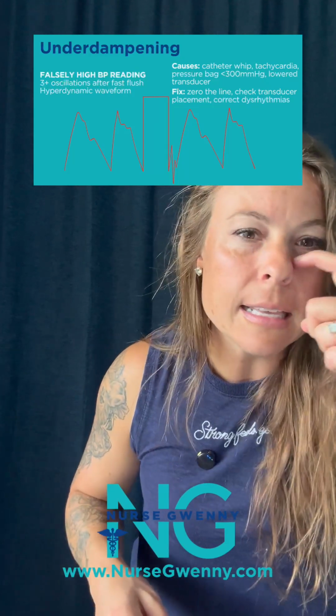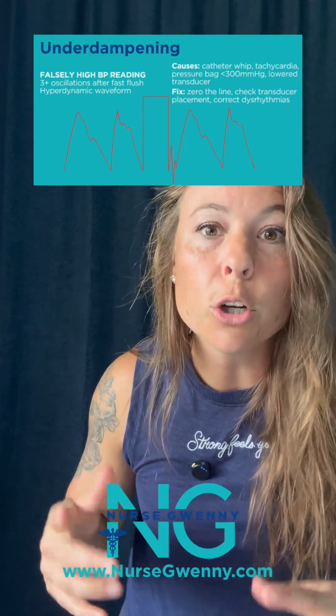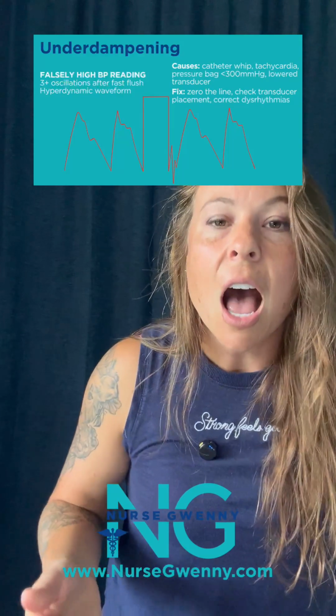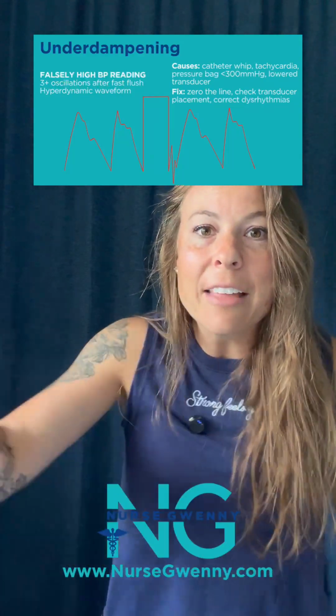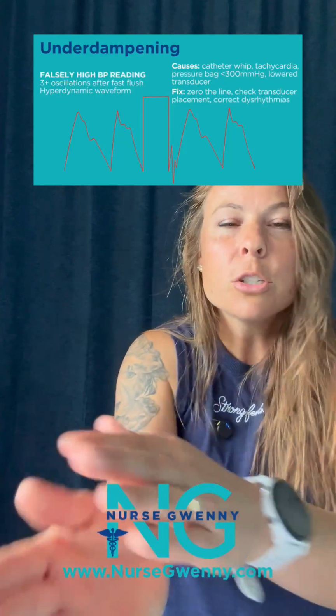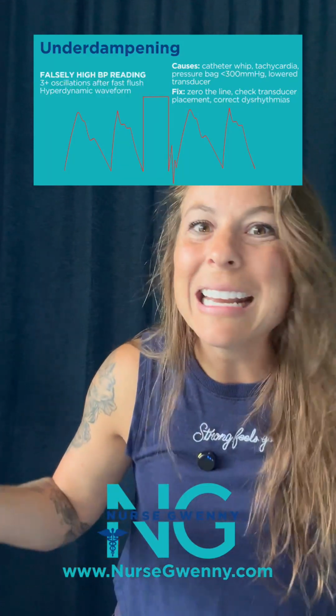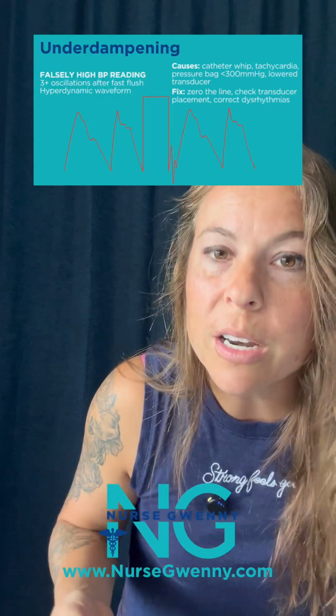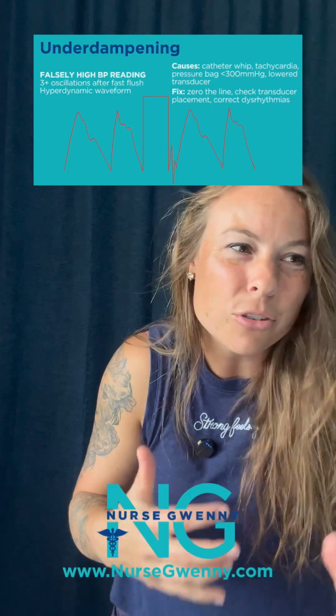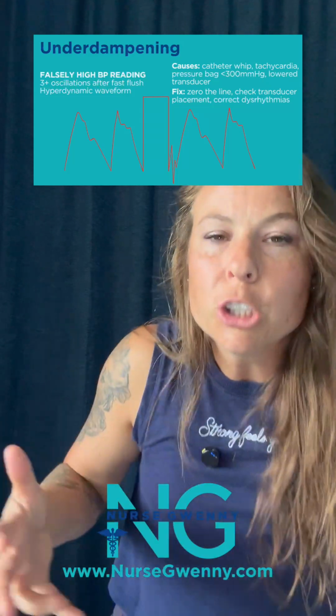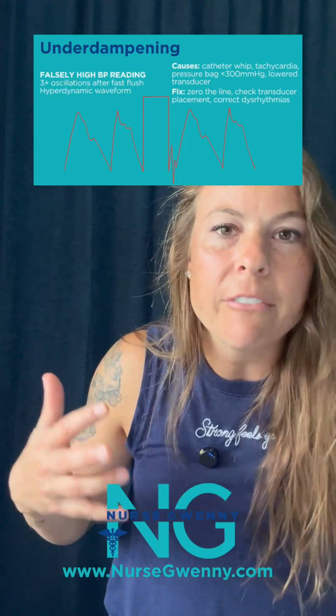So some things that can cause this: if the patient is in a ventricular arrhythmia, that can cause underdampening. If there's catheter whip and it's flapping around there, so make sure your patient's arm again is positioned appropriately. You can do another one of those fast flush tests, and that'll make sure everything is clear in the line. We don't have anything interfering with it.